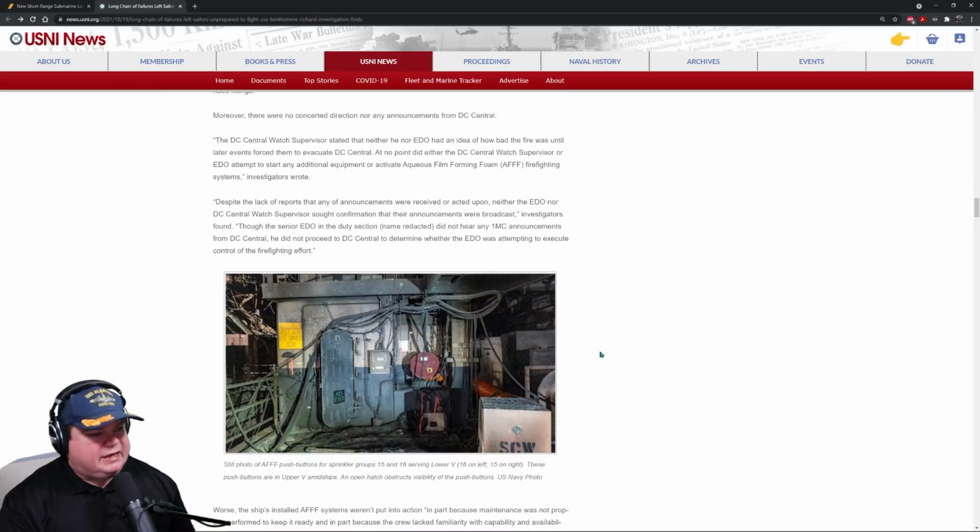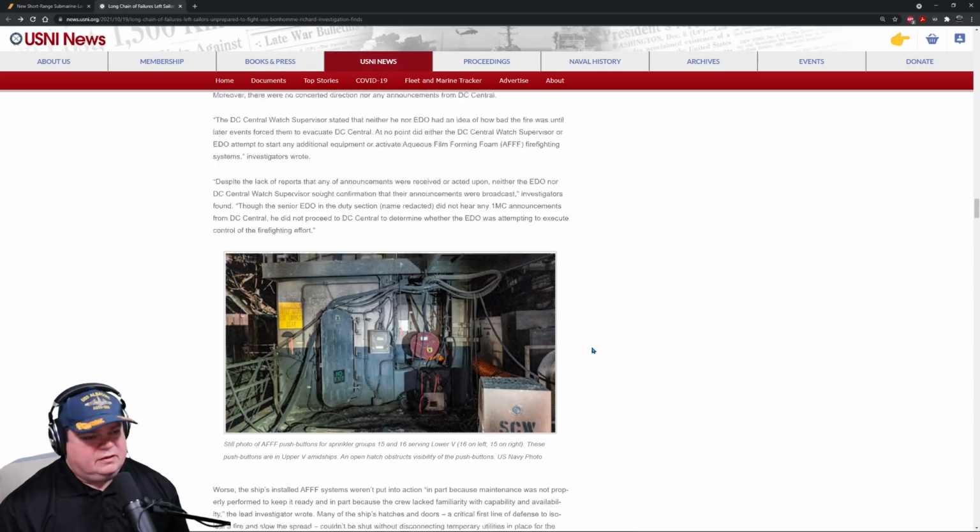Anyway, despite the lack of reports from any announcements that were received or acted upon, neither the EDO nor the DC Central Watch Supervisor sought confirmation that their announcements were broadcast. So because of the problems with the 1MC, it's possible that they were making announcements that nobody heard, or very few people heard. Quote, "Though the senior EDO in the duty section, name redacted, did not hear any 1MC announcements from DC Central, he did not proceed to DC Central to determine whether the EDO was attempting to execute control of the firefighting efforts." So that's interesting.